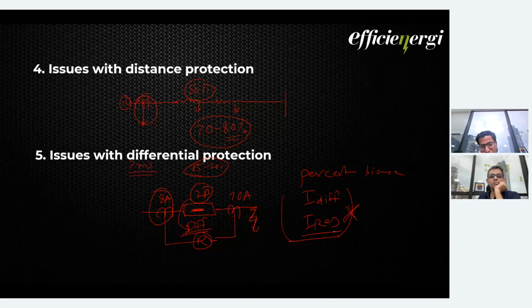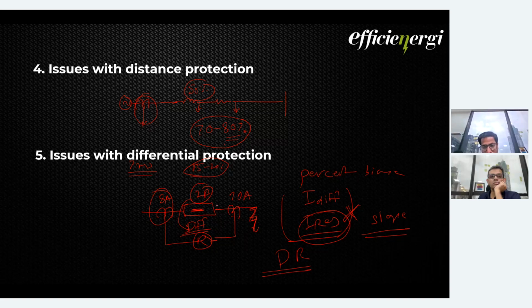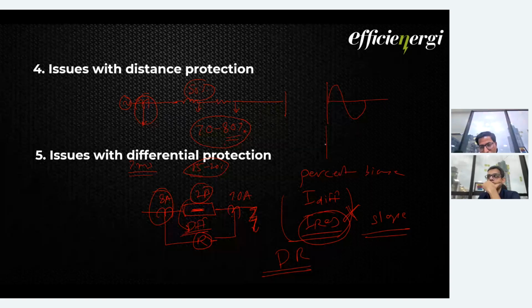For the present, you can understand that if your differential is activating for an external fault, you must look into your restraint settings or the slope settings. At the same time, you must check your disturbance recorder for CT saturation on both sides. Both sides means, let's say on one side this is your current, and on the second side it is something else, so that CT is saturating. Then we have to replace it immediately.